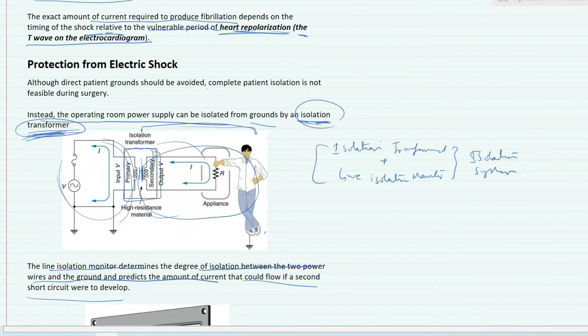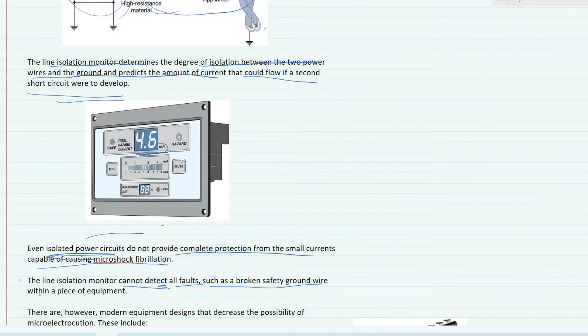But even isolated power circuits do not provide complete protection from small currents capable of causing microshocks or fibrillation. This can happen through capacitive couplings, as already discussed. The line isolation monitor can detect some faults, but it cannot detect all faults, such as broken safety ground wires within a piece of equipment.